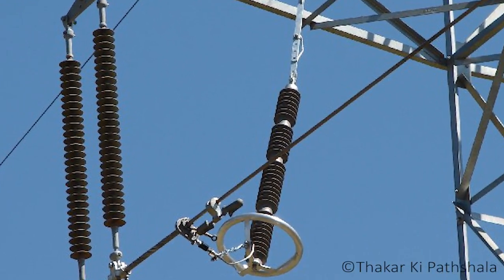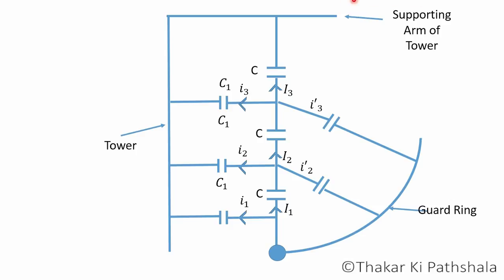Then there is the third method: to use guard rings. The voltage level across each unit in a string can be equalized by using a guard ring, which is a metal ring electrically connected to the conductor and surrounding the insulator disc. The guard ring adds some capacitance between the metal fittings and the line conductor. It is positioned in such a way that the current flowing from the guard ring equals the flowing shunt capacitance currents, and these currents are added into the currents flowing through the mutual capacitance. So the current flowing through each disc remains equal and ultimately we get better string efficiency.